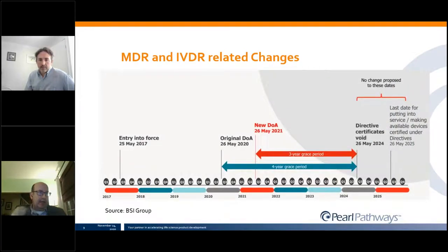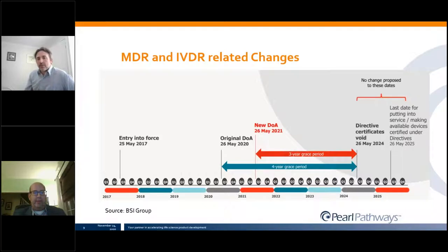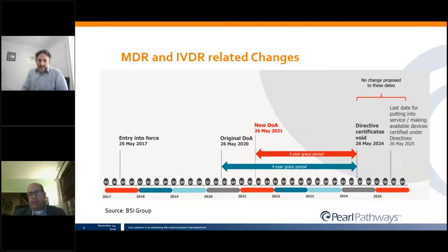Looking at the timeline graphically — based on a schematic provided by BSI — the original date of application, which would have been May 2020, has been moved to May 2021. Directive certificates will still become void by May 26, 2024. So if your product has a current unexpired EC certificate under the directive, you would have until May 2024 for that product to be on the market. After that date, you would need to comply with the MDR from an assessment perspective.